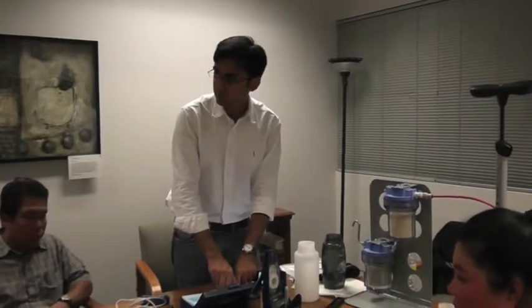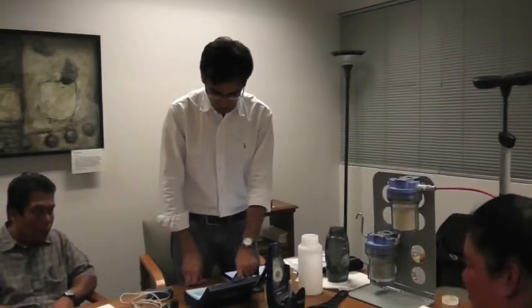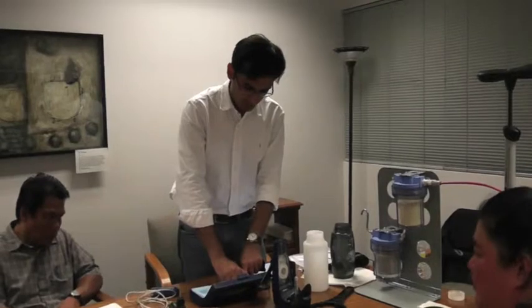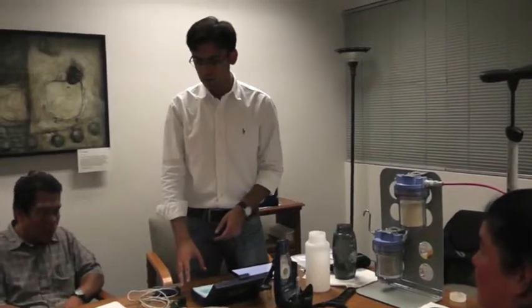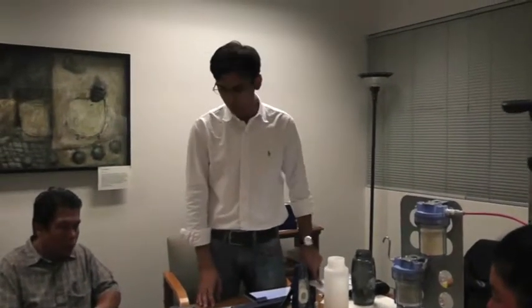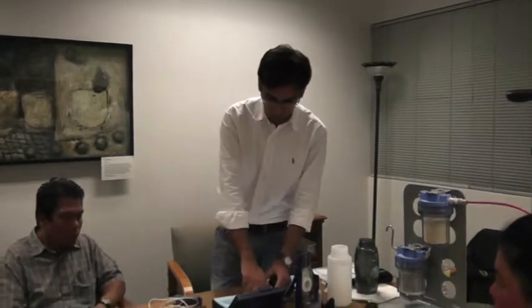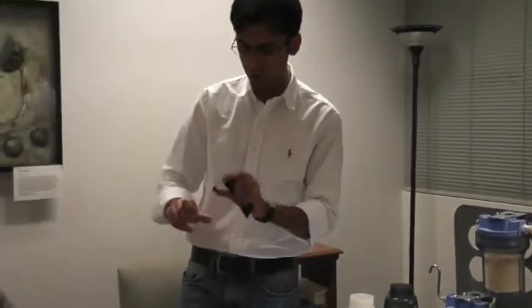That's your turbidity kit there with all the little vials and everything? Yes. It comes with a little booklet telling you how to calibrate the system. Right now the system is calibrated. To do that, they have given this water, just like 100 NTUs. NTU is the unit of measurement of turbidity. I forget what the N stands for, but turbidity unit. So this is the 100 NTU turbidity vial that they have provided with the kit.